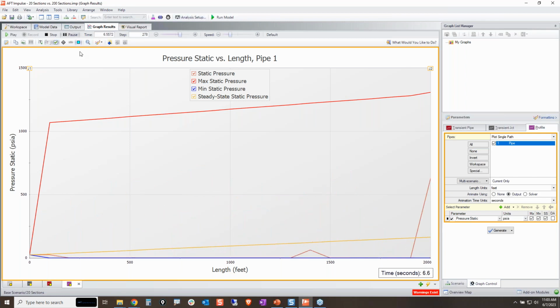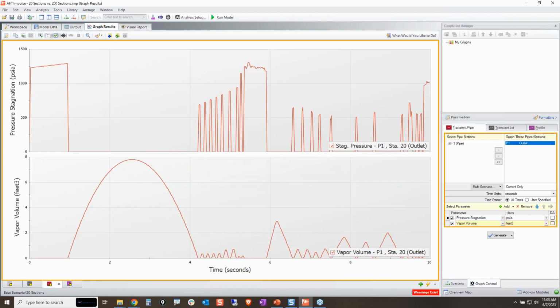Okay, now, because I'm only using the discrete vapor cavity model, I'm not going to try and fully understand and evaluate these results because there is so much cavitation going on. This is just important to teach you how to start looking at your cavitating results. So when you start looking at the valve itself and you see all this happening, that's because of all the cavitation that's going on inside the piping.